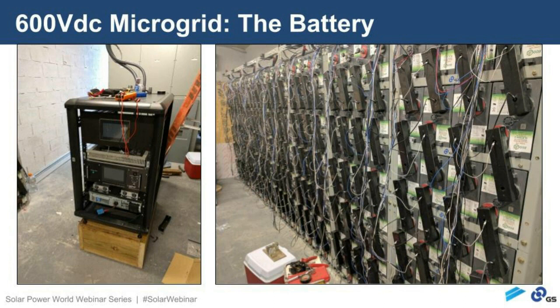This is a very large, essentially 2-volt based battery running at about 500 volts, and it also has to have a BMS, which monitors every single cell, just like a lithium BMS does. So what we needed to do was create a firewall that determined the battery state of health and state of charge, and had the final say on when and if the battery could be connected, and what its state of charge was. Once we finalized that design, we turned it over to the energy management system, which could then reliably call on that battery to charge or discharge based on its own calculated state of charge.